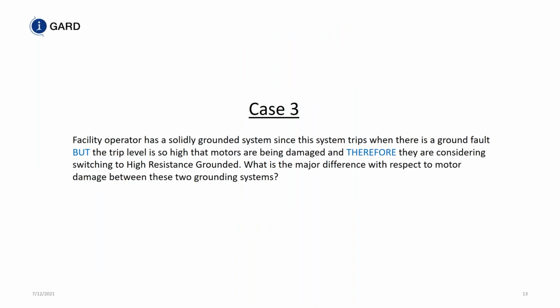So facility operator, case number 3, has a solidly grounded system, and the system trips when there is a ground fault, but the trip level is so high that motors are being damaged, and therefore they want to consider switching to high resistance grounding. What are the major differences with respect to motor damage between these two grounding systems?